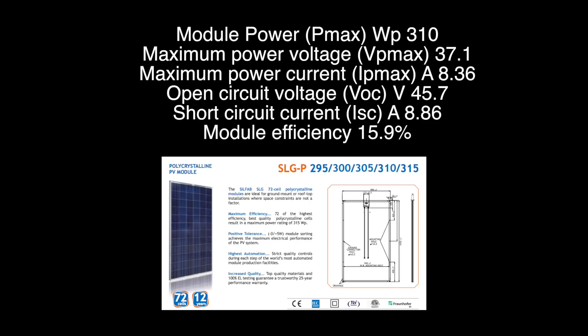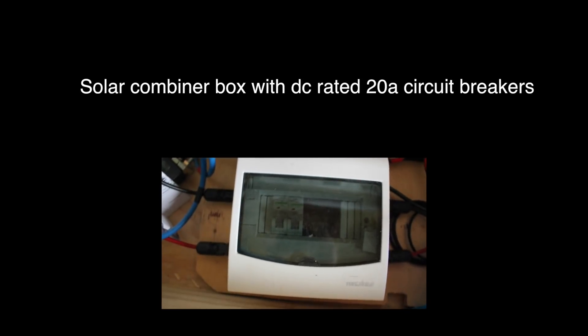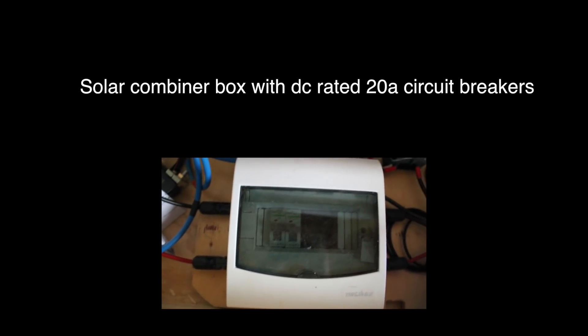I have three 310-watt panels connected in series, giving me 930 watts at 111 volts. The power coming in from the solar panels goes through a 20-amp DC-rated circuit breaker.